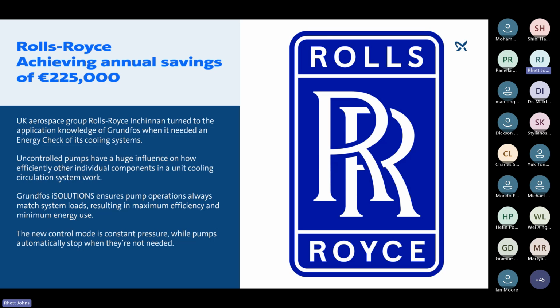And what we did is, again, an energy optimization audit on the site. We found out which systems are running maybe a little bit too hard relative to the cooling requirements. We also looked at the chiller components and the systems that are meant to control the temperature within Rolls-Royce, and we suggested different changes to the control strategy that they had. And we resized and reduced the size of the pump at Rolls-Royce, and we ended up with a 225,000 euros reduction in energy consumption on site.